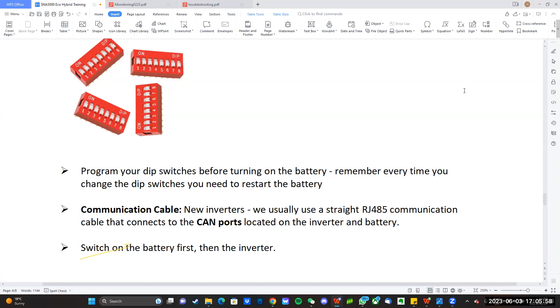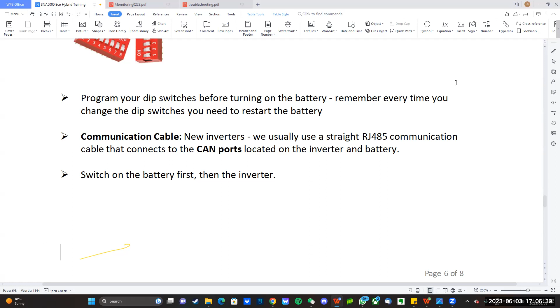To emphasize this: sometimes, and this is very possible, you may have purchased a battery with a faulty BMS, and because of this faulty BMS it could cause a short circuit on the inverter and damage the MOSFETs on the DC-DC side, which is very nasty. It's also tricky to get around, especially for warranties, as it's a back and forth getting the situation sorted out. So please make sure you switch on the battery first and then the inverter.